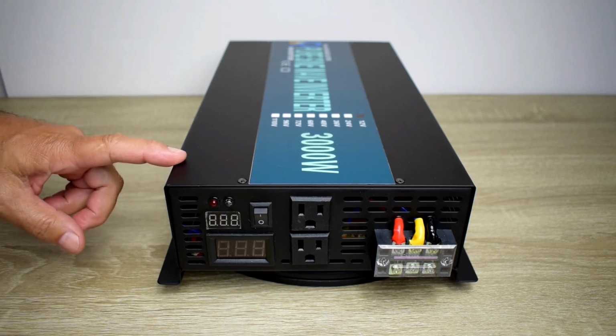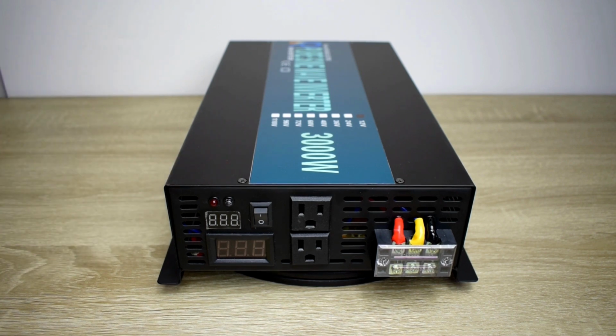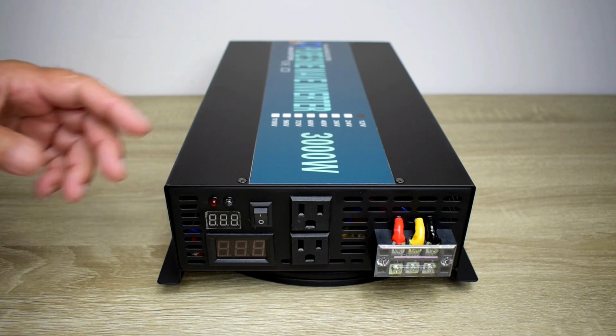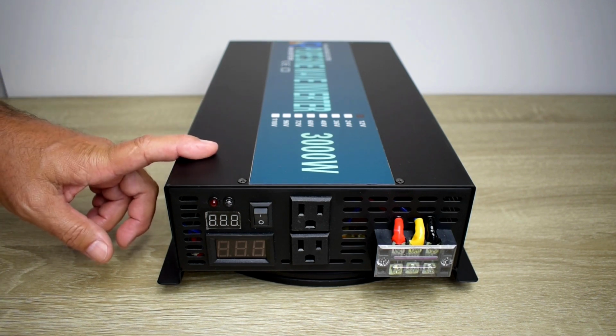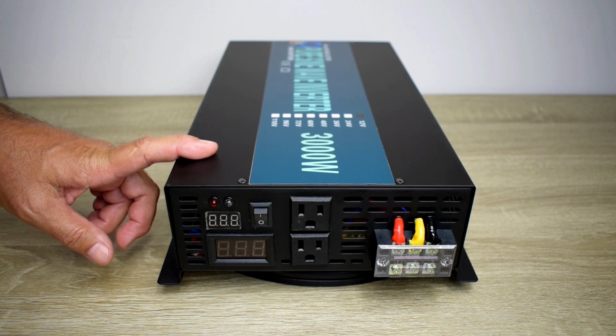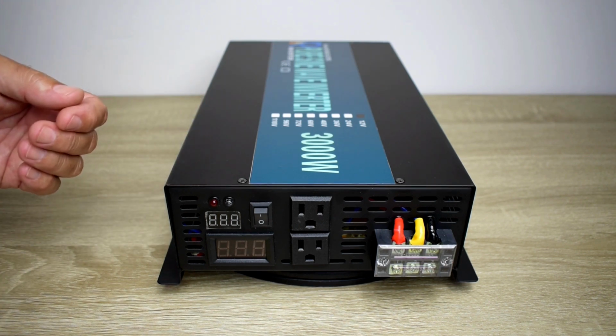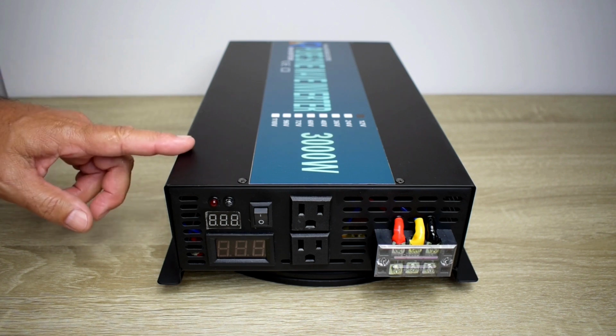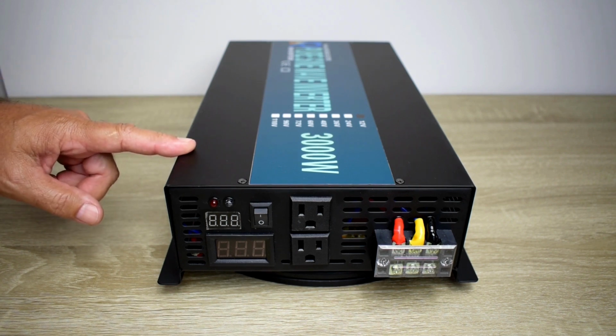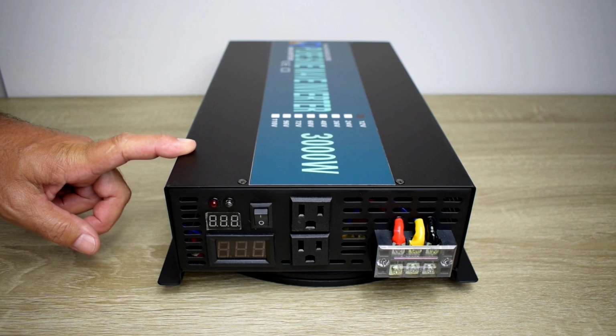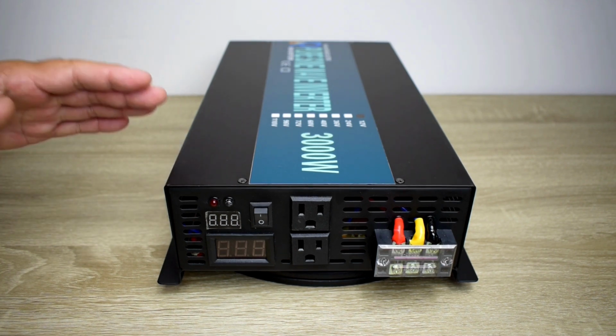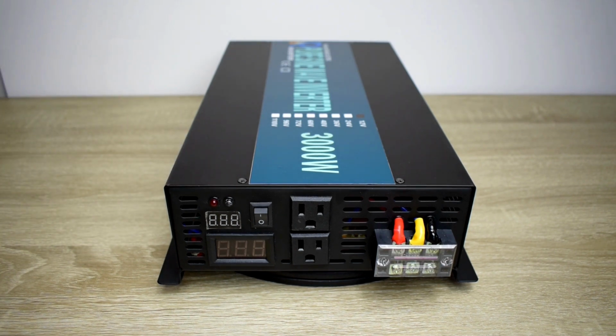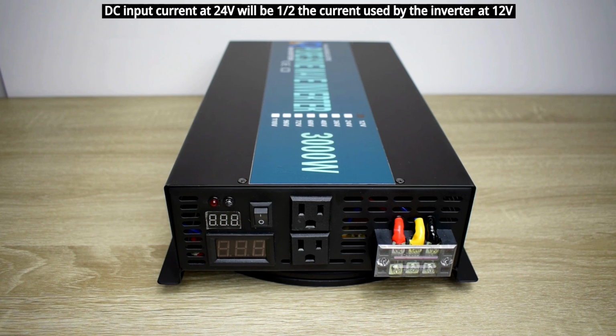This one is for a 12 volt DC input, ideal for recreational vehicles, large inboard boats, and trucks. For off-grid solar power systems, I recommend a 24 volt or 48 volt input version. Using an inverter with a 24 to 48 volt input along with an MPPT charge controller is the way to go—you'll have lower losses in the wiring, and the wires used can be smaller in diameter due to lower current, which saves you money.